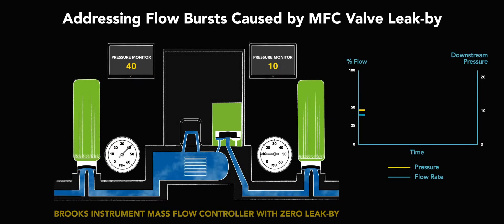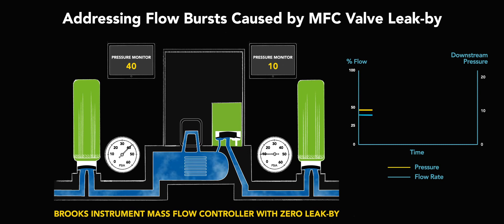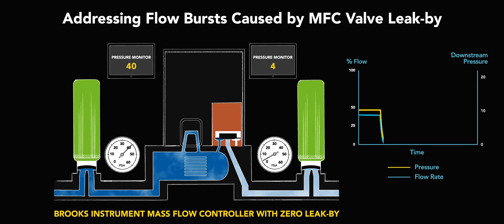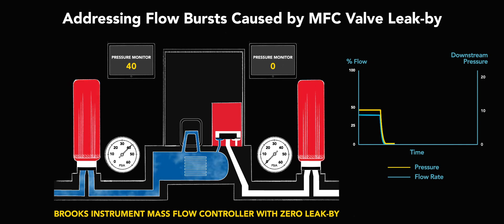A command setpoint is sent to the MFC to control the desired gas flow rate going into the process chamber during this recipe step. A zero command setpoint is then sent to the MFC, closing the MFC valve. The MFC valve and isolation valves are now all closed. The process recipe is now complete.